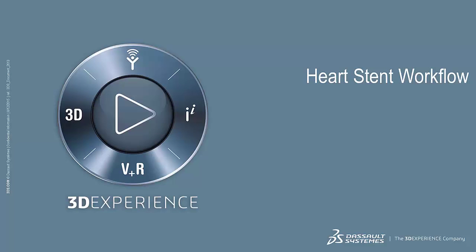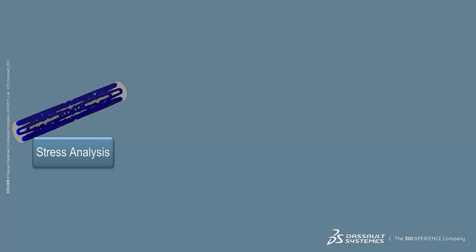Today, we're going to talk about stent design optimization, a showcase workflow developed for this specific process. Design of a new coronary stent involves consideration of various performance criteria, including radial stiffness, durability, crimpability, and material and manufacturing choices, among others. As it is time-consuming and expensive to evaluate and optimize a stent design by means of prototyping and physical testing, computer simulations offer powerful techniques to conduct virtual optimization of stent designs early during device development.